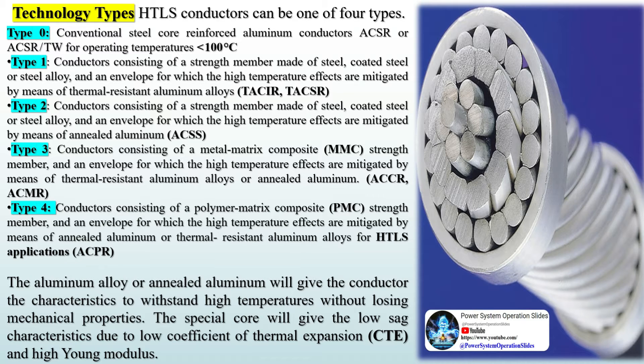HTLS conductors can be one of four types. Type 0: conventional steel core reinforced aluminum conductors (ACSR or ACSR-TW) for operating temperatures less than 100°C. Type 1: conductors consisting of a strength member made of steel, coated steel, or steel alloy, and an envelope for which the high-temperature effects are mitigated by means of thermal-resistant aluminum alloys (TACIR, TACSR). Type 2: conductors consisting of a metal matrix composite (MMC) strength member, and an envelope for which the high-temperature effects are mitigated by means of thermal-resistant aluminum alloys or annealed aluminum (ACCR, ACMR).